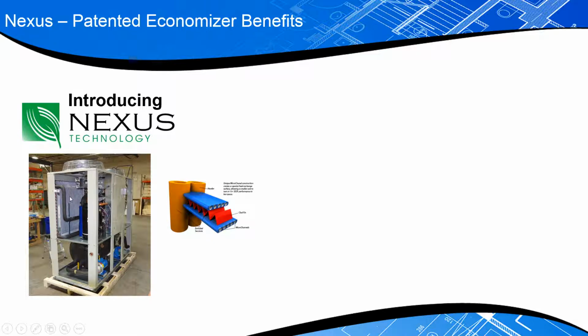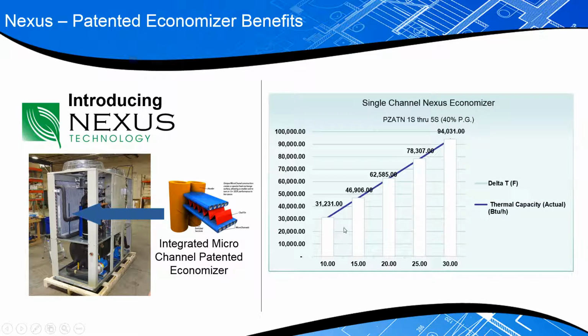Now, one thing to keep in mind is we cannot operate this particular design in both economizer and mechanical at the same time. Our PLC will sort all that out, but that does not happen in this particular design. So this is a quick graph here on the savings.